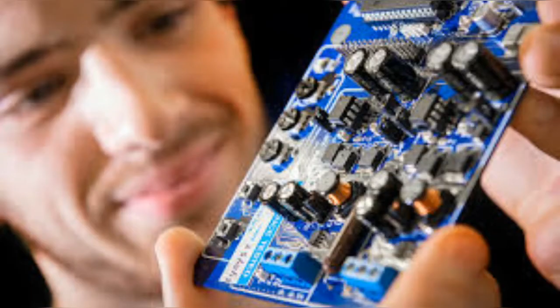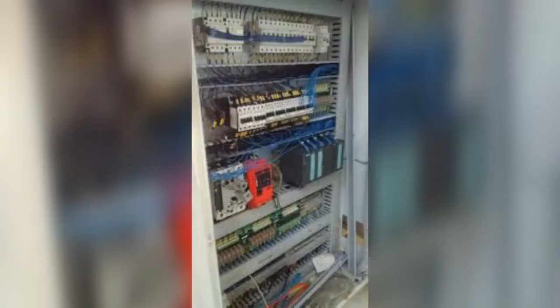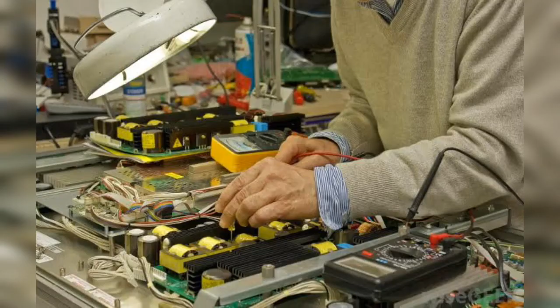The power analysis must always be at the very top of your task. In the design of an electrical installation, the source must be sized according to the purpose of the installation, the continuous use of a circuit, and the receiving supply. This is based on the knowledge of power consumed, to choose the service requirement and the source, meaning what the consumer or customer requires, based on the consumption of power and what kind of apparatus are used.